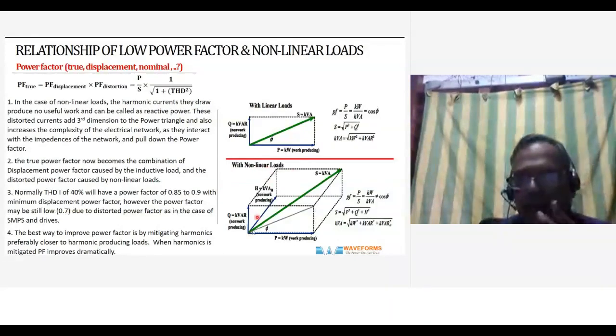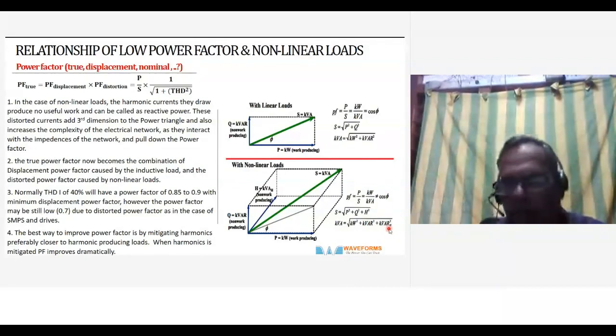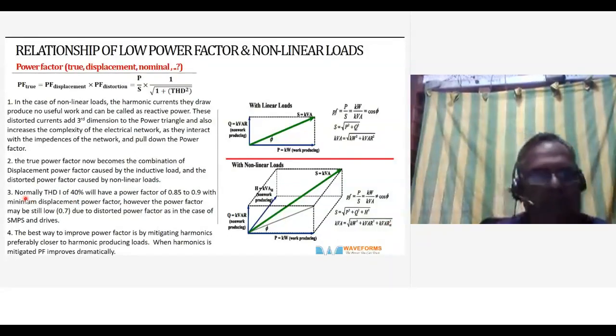So you have another kVAr square, which is the harmonic kVAr. So kVA is equal to kilowatt square plus kVAr square due to displacement, plus kVAr square, which is the distorted reactive energy. All reactive energy is not usable; it is just wasted, and it circulates between the load and the source. Each time it keeps reversing, forward and back, you keep losing energy. That's where it heats up the cables and the transformers.